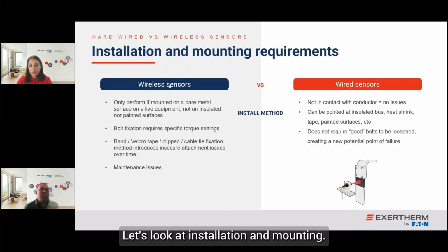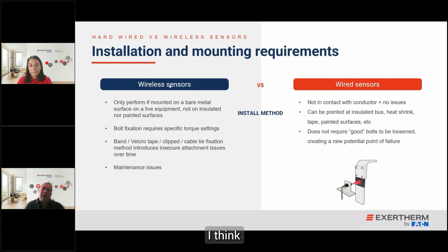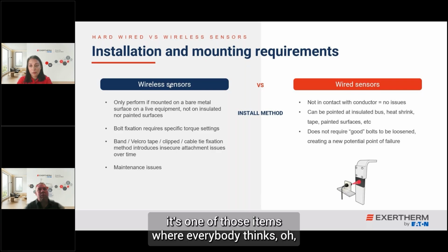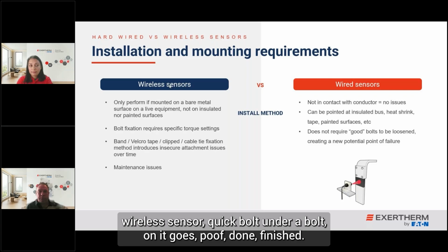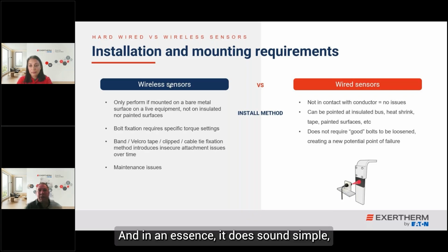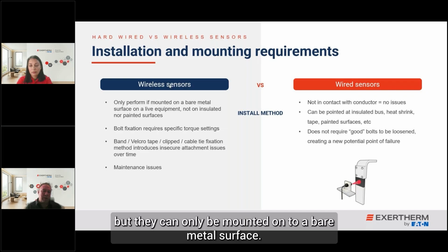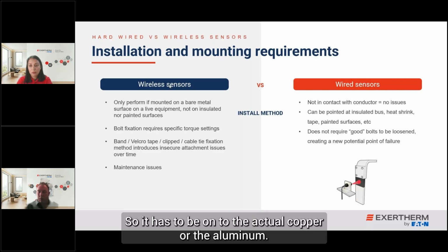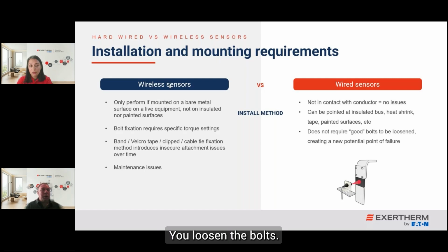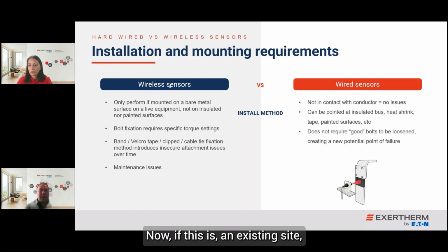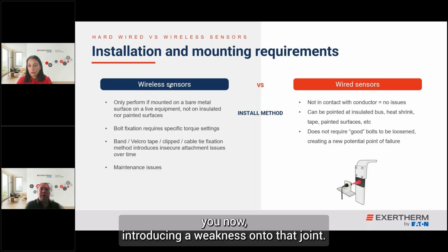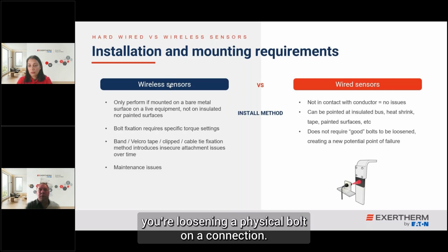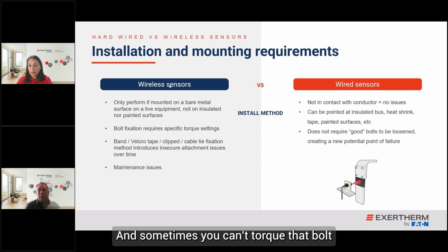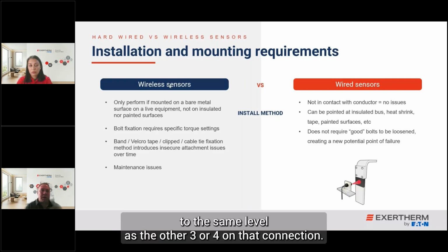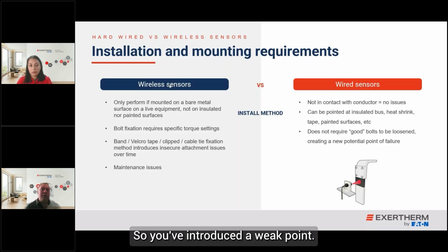Let's look at installation and mounting. I think it's one of those items where everybody thinks, oh, wireless sensor, quick bolt, undo a bolt, on it goes, done, finished. And in essence, it does sound simple. But they can only be mounted onto a bare metal surface. So it has to be onto the actual copper or the aluminium, the connection point. You're loosening a bolt. Now, if this is an existing site, you're now introducing a weakness onto that joint. You're loosening a physical bolt on the connection. And sometimes you can't torque that bolt to the same level as the other 3 or 4 on that connection. So you've introduced a weak point.